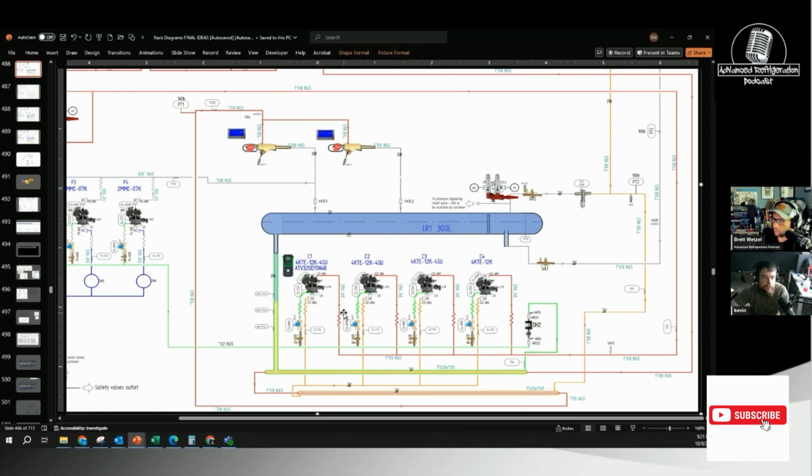But anyway, what it's doing is putting the oil all the way through the system, going up and getting dropped into the flash tank. The reason this is okay is because PAG operates opposite of regular POE oil, in that it will actually sit on the bottom of the liquid. PAG oil is used in ammonia. They do basically the same thing. They have oil pots at the bottom that catch that oil, and they usually just get rid of it. But in this case, we're reutilizing it.